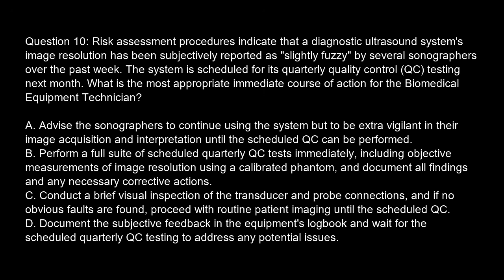Option A. Advise the sonographers to continue using the system, but to be extra vigilant in their image acquisition and interpretation until the scheduled QC can be performed. Option B. Perform a full suite of scheduled quarterly QC tests immediately, including objective measurements of image resolution using a calibrated phantom, and document all findings and any necessary corrective actions. Option C. Conduct a brief visual inspection of the transducer and probe connections, and if no obvious faults are found, proceed with routine patient imaging until the scheduled QC. Option D. Document the subjective feedback in the equipment's logbook and wait for the scheduled quarterly QC testing to address any potential issues.